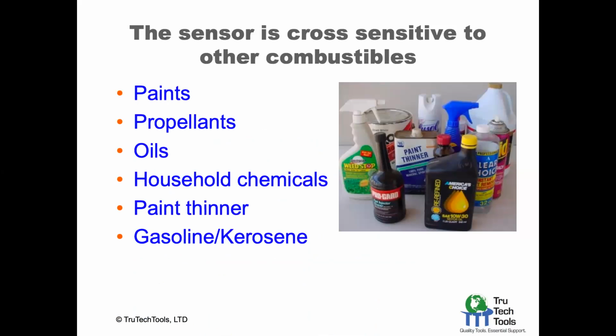So we talked about volatile chemicals. Other volatile chemicals have combustible gases in them. They can be cross-sensitive for the product. So things like paints, propellants, oils, chemical cleaners, paint thinners, gasoline, kerosene, they can all cause the product to react. If that's the case, you should know it because you're around those products, and they may be giving you a false signal. So again, this is operator awareness where you use the products.